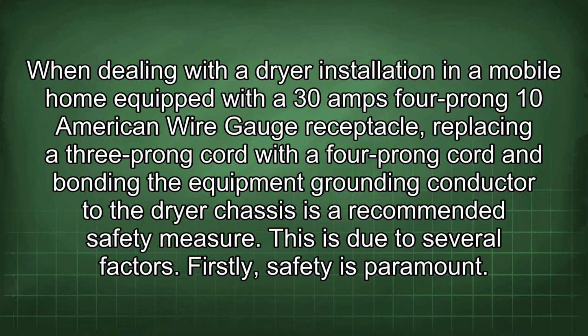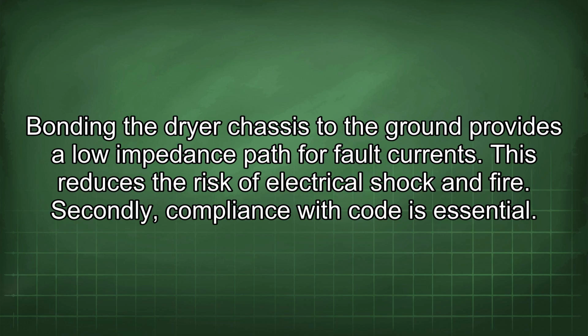When dealing with a dryer installation in a mobile home equipped with a 30 amp, 4-prong, 10 American wire gauge receptacle, replacing a 3-prong cord with a 4-prong cord and bonding the equipment grounding conductor to the dryer chassis is a recommended safety measure. This is due to several factors. Firstly, safety is paramount. Bonding the dryer chassis to the ground provides a low impedance path for fault currents. This reduces the risk of electrical shock and fire.